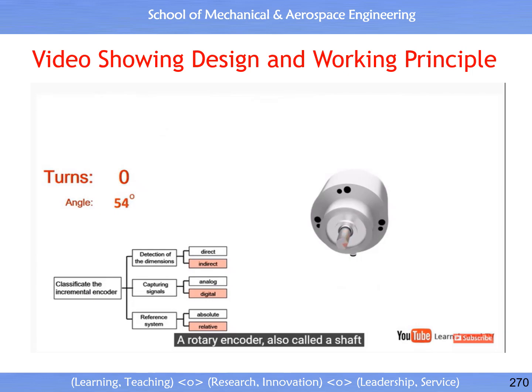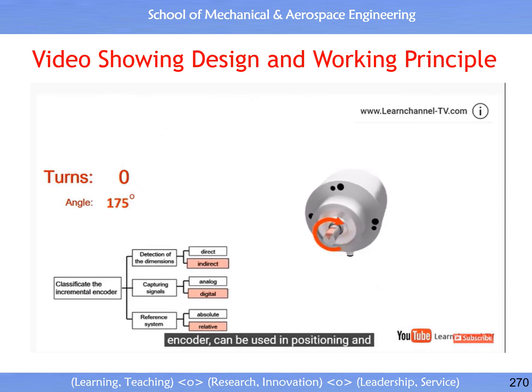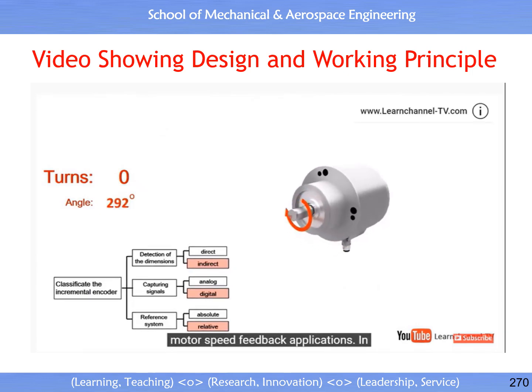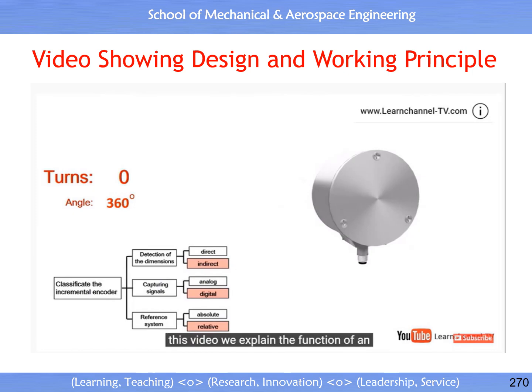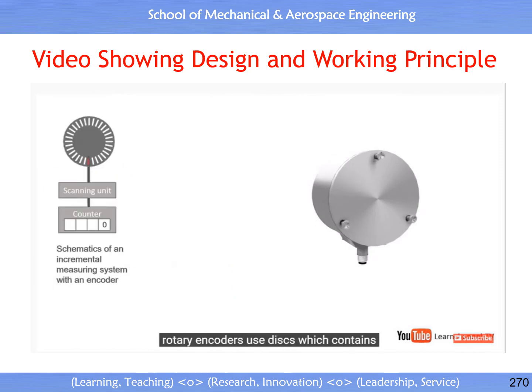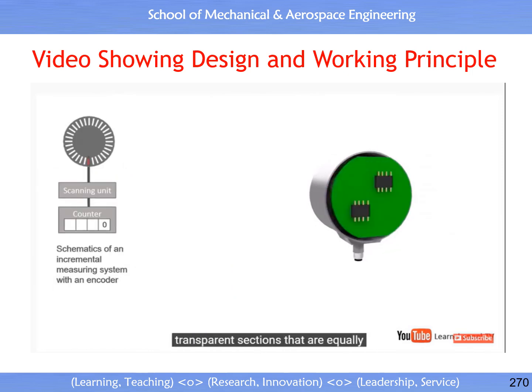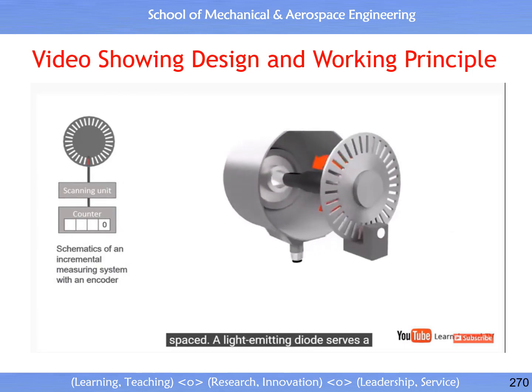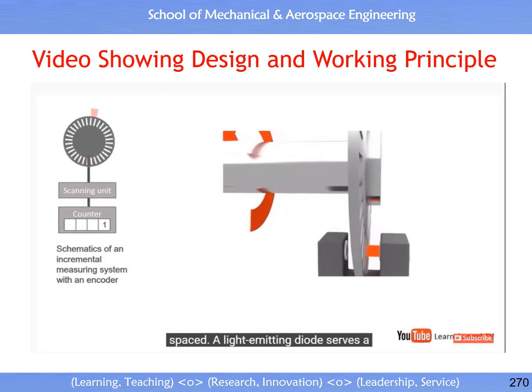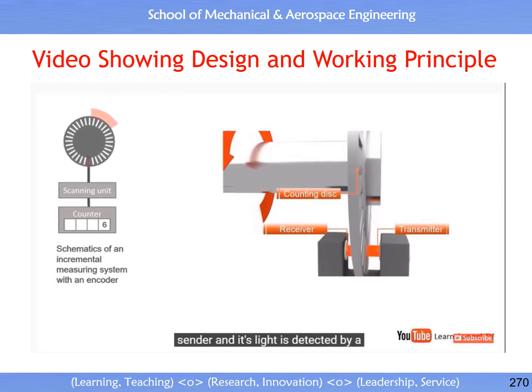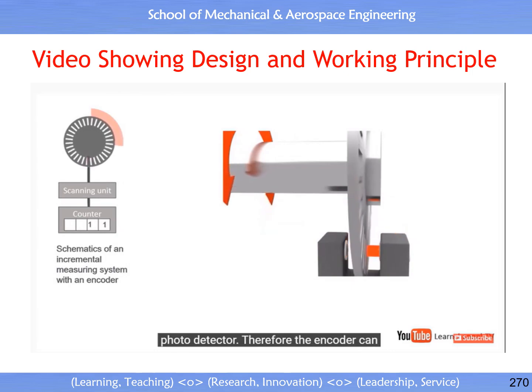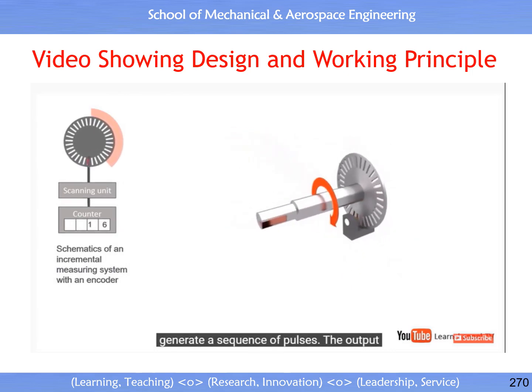A rotary encoder, also called a shaft encoder, can be used in positioning and motor speed feedback applications. In this video, we explain the function of an incremental rotary encoder. Incremental rotary encoders use discs which contain transparent sections that are equally spaced. A light-emitting diode serves as sender and its light is detected by a photodetector. Therefore, the encoder can generate a sequence of pulses.